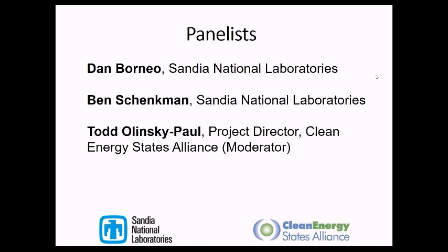Ben, you want to add to that? Yeah, you should have a controller that knows that when it's connected to the utility, it can act like a current source, or maybe a voltage source type energy storage system. But once it loses voltage from the utility, it can go into emergency mode and do what it needs to do in a microgrid. It might become grid forming, a voltage source giving power to the critical load, or it might work with a generator startup, just doing a grid stability type mode, looking at frequency and voltage, maintaining 60 hertz and 1 per unit voltage.